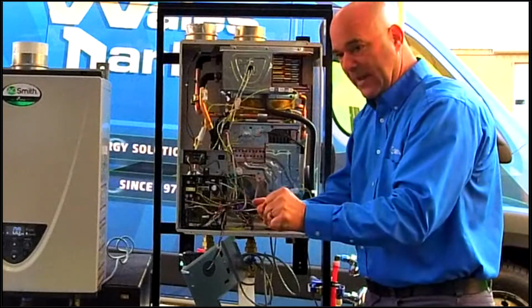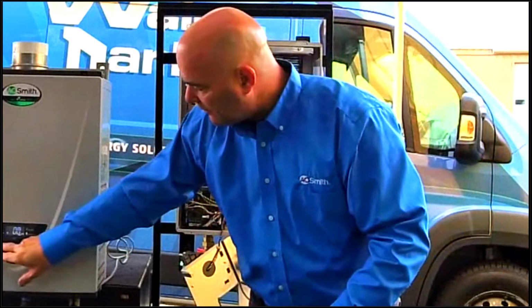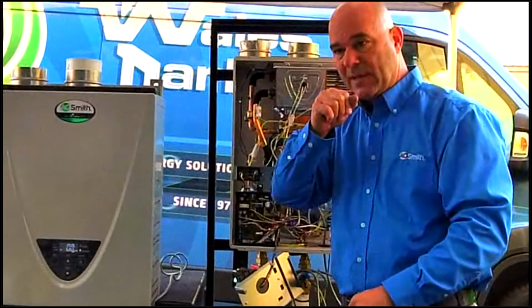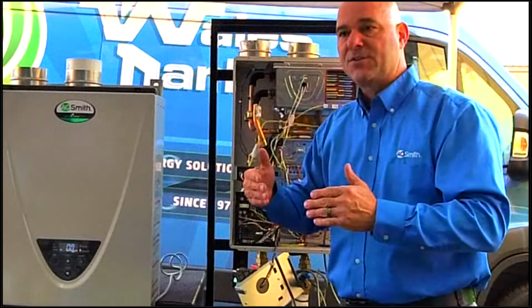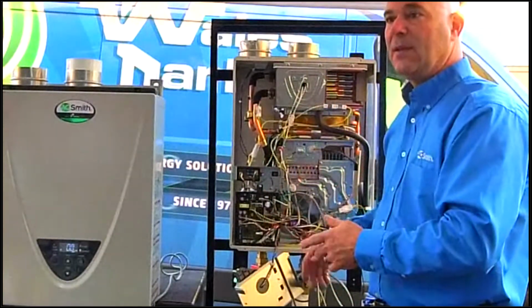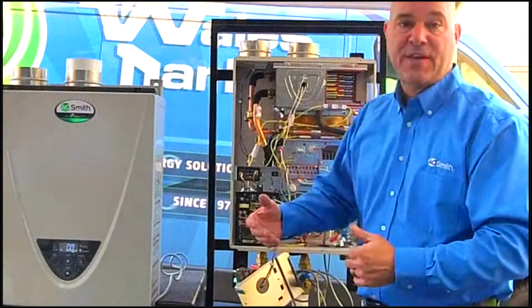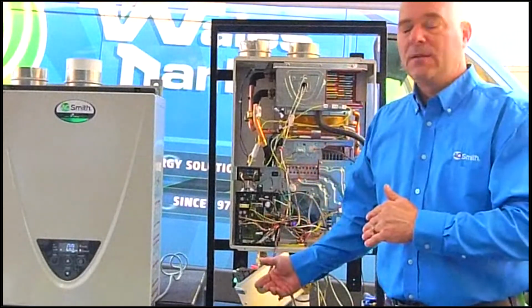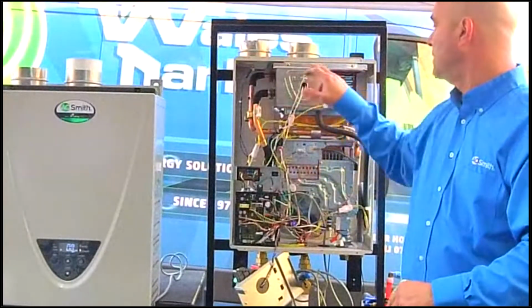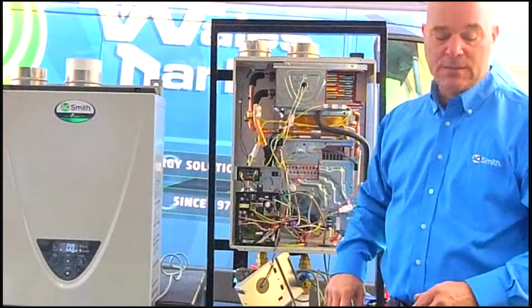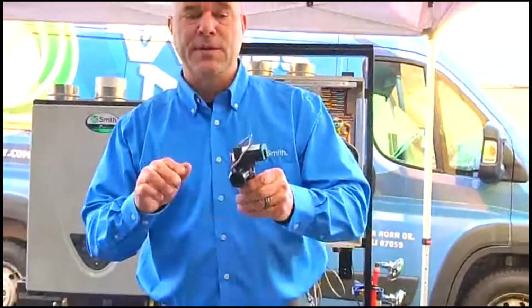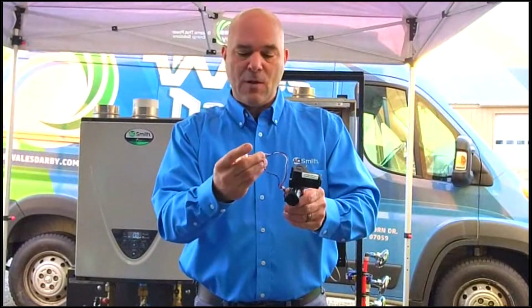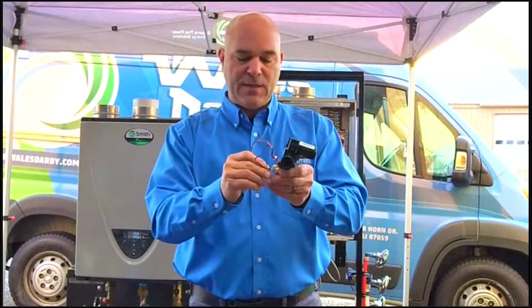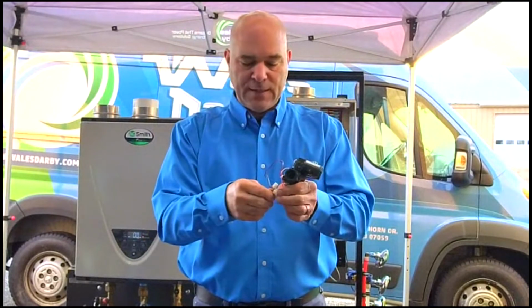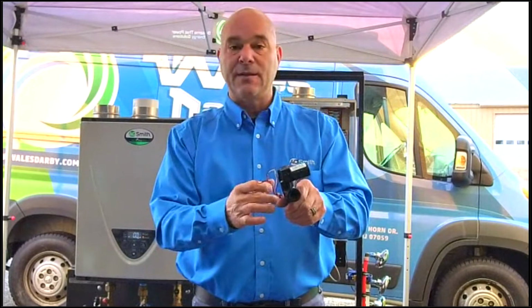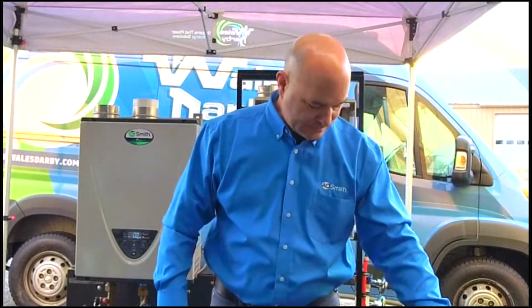You can power it back up with your mains still off. Hit your info button till you get the flow. You can blow into the flow meter and see if it registers flow. If it registers flow, you know the flow meter is working. It's something else. If it does not register flow, you know your flow meter has failed and you need to replace your flow meter. Okay, so that's a pretty easy check. Really no tools, a Phillips head screwdriver to take the cover off. Okay, so that's the job of the flow switch. That's what's in there. That's what it does. 2 Molex connectors. There are some other ways to check this if need be, but I gave you the basic, real easy, simple, let's get this thing checked out and move forward method of checking the flow switch.